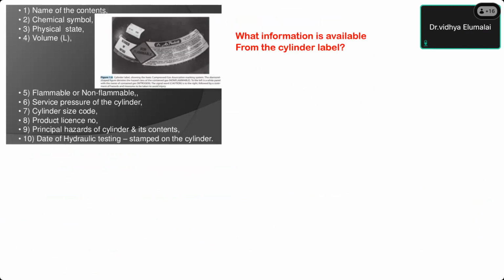What information is available from the cylinder label? The type of the cylinder, the identification of the gas, date of manufacturing, pressure, date when the pressure test was done, date of validity. So these are all the things: name of the contents, chemical symbol of the contents, physical state, whether it is a gas or liquid, what is the total volume, whether it is flammable or non-flammable, what is the service pressure of the cylinder, size code, product license number, principal hazards of the cylinder and its contents, and date of hydraulic testing stamped on the cylinder. So these are all the points that you will get by looking at this portion, where there will be a label or a collar on the neck of the cylinder.